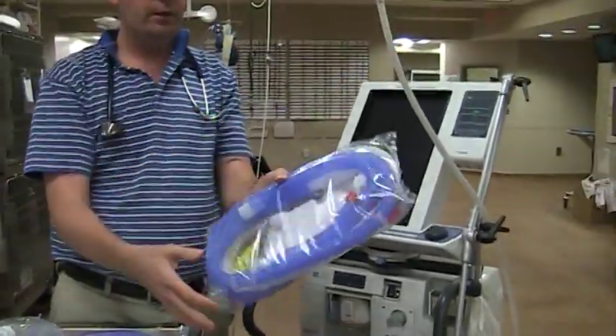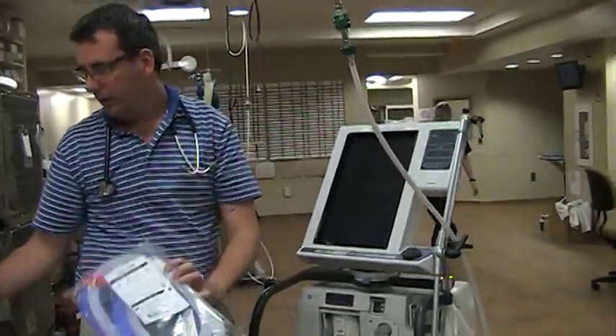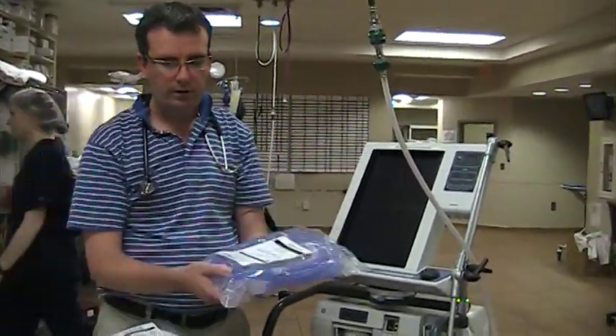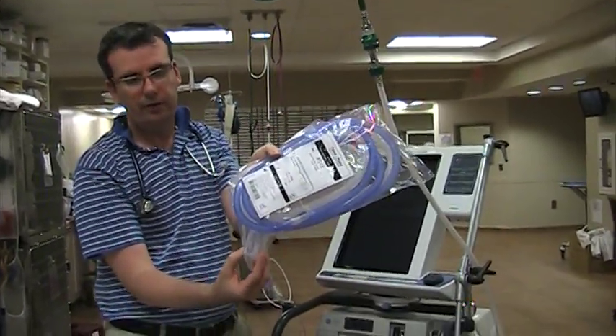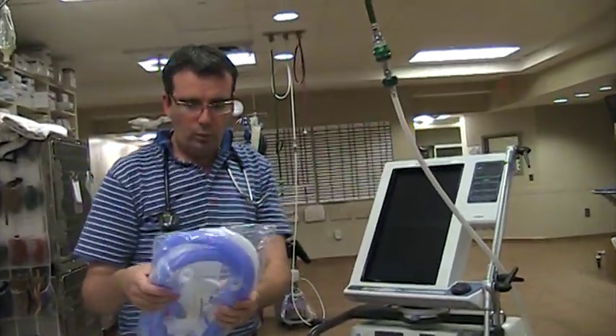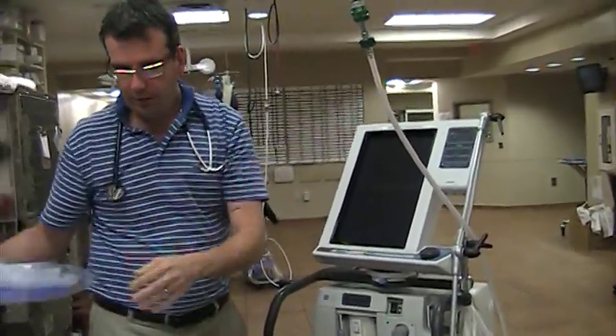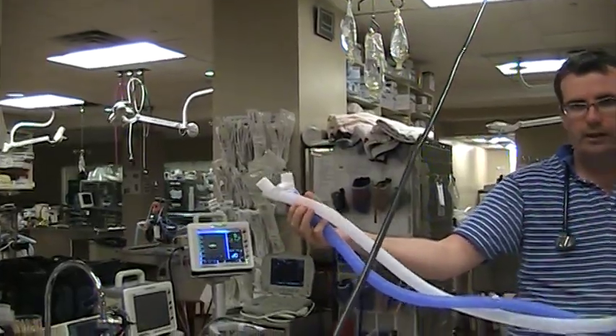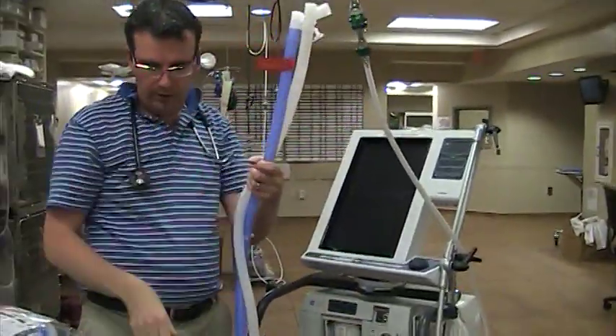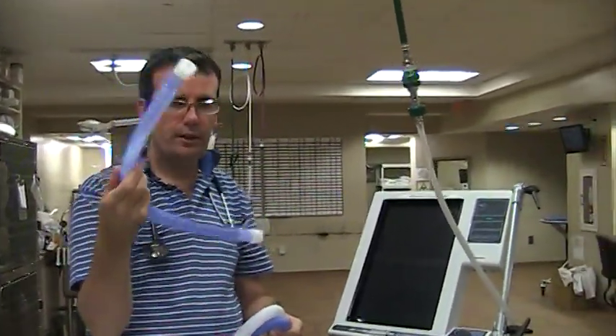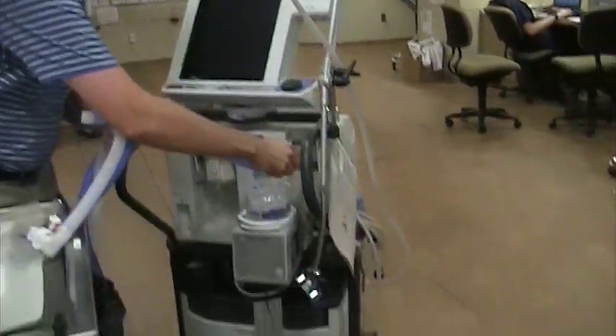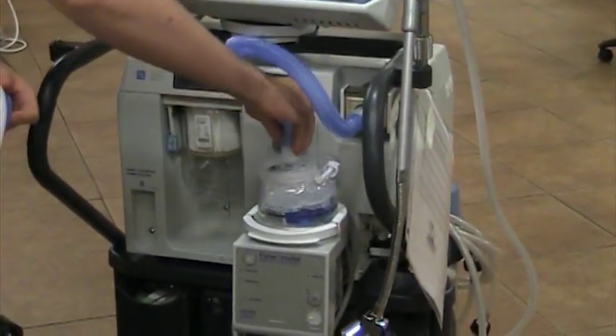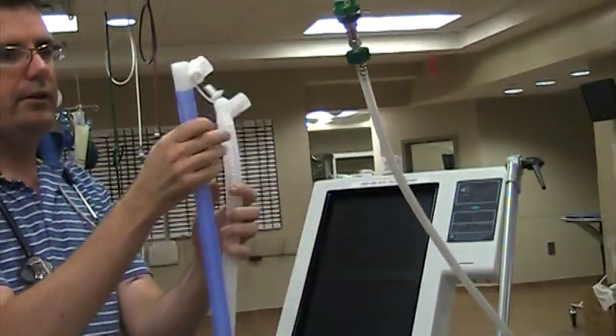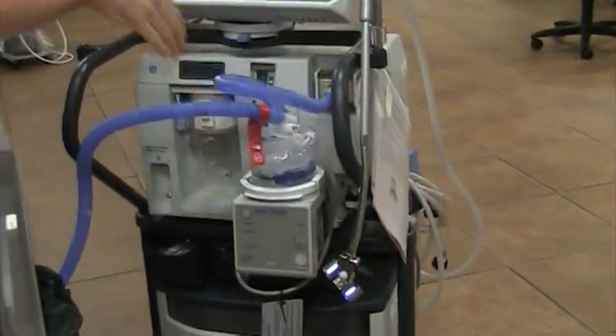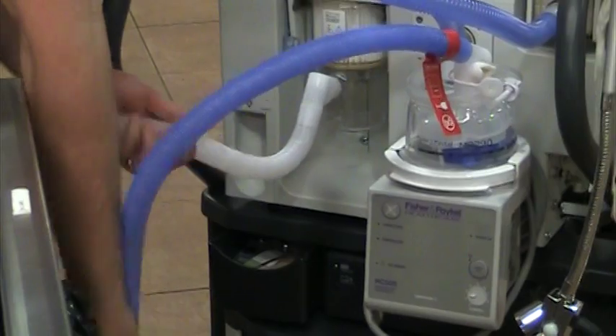There are two basic types of tubing. There is the adult set, which is wider tubing, and then there's the neonatal set, which has narrow tubing. The other difference is that the neonatal set on the expiratory limb has a water trap there as well. So basically you open this up. I already have one that's opened up. The blue is the inspiratory line, the clear or white line is the expiratory line. And then inside there's also another short tube which attaches the inspiratory filter to the humidifier. So that's what we're going to do right now. Inspiratory filter attached to the humidifier, and then we attach the inspiratory line to the humidifier, and then the expiratory line to the expiratory filter.